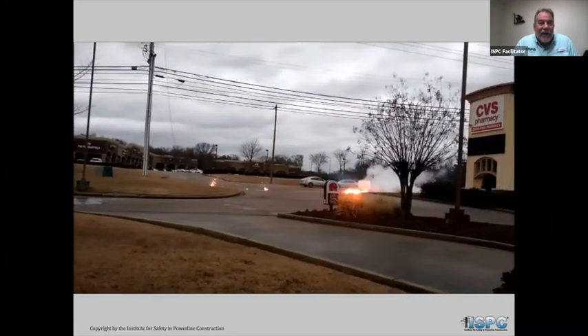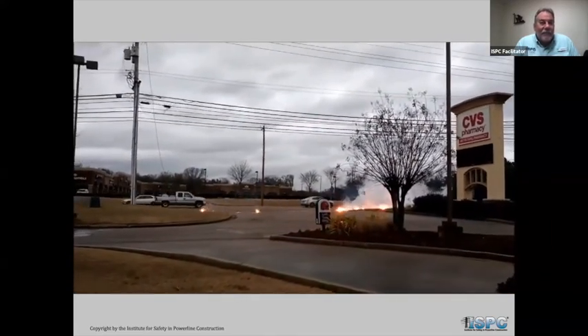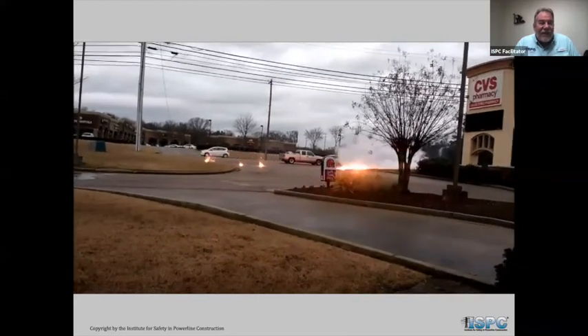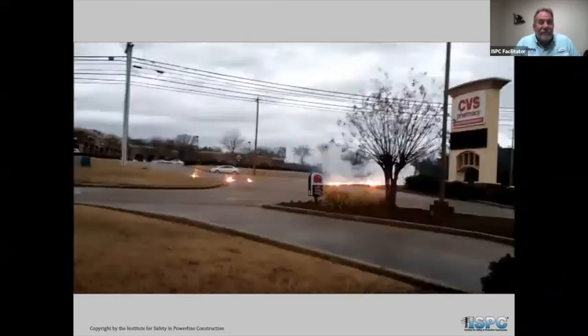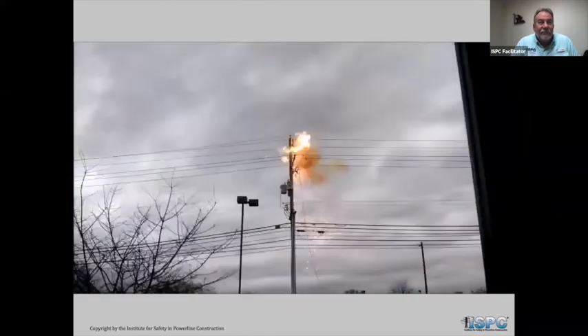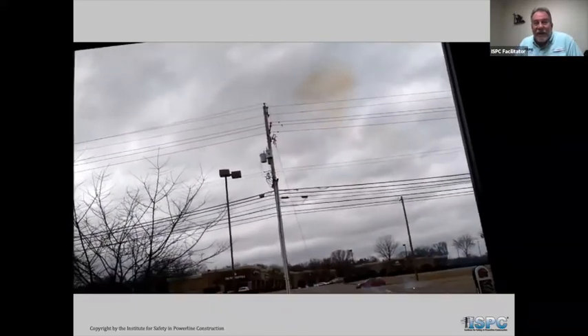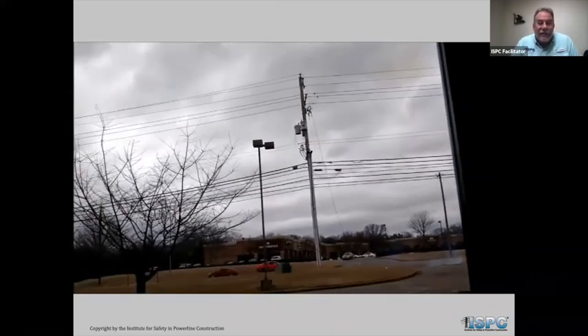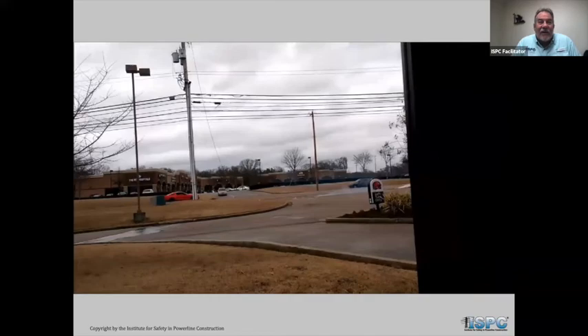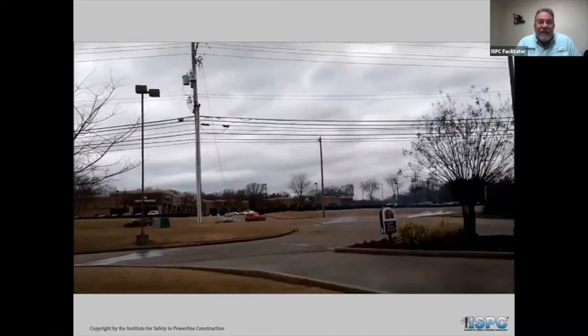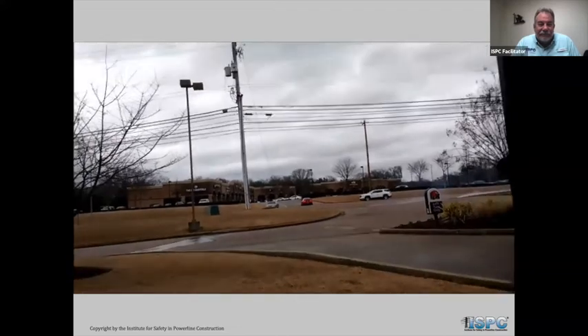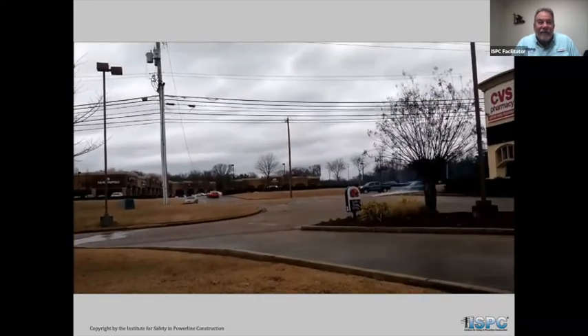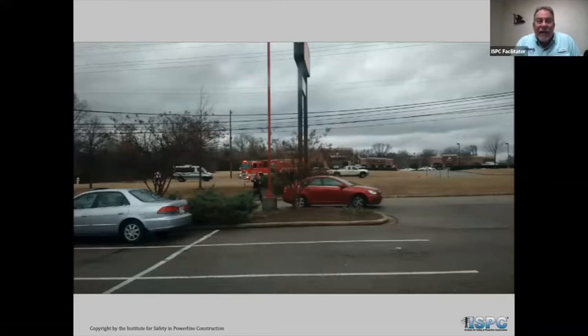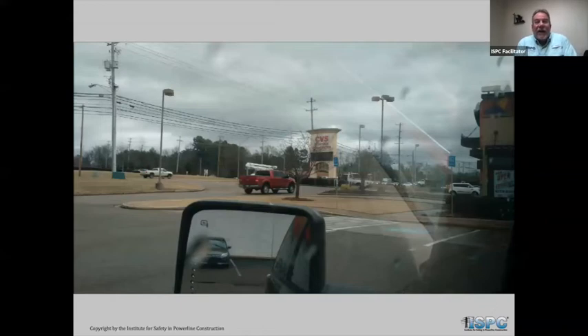During this, you can see that no one drives across it, but here it is, energized again. Yeah, I saw it fall, it came loose from that pole there. So there it just went phase to phase through that 3-phase transformer. So now you see all 3 cutouts are hanging down, but is the line de-energized now? I don't know. It depends on the company's scheme and how many times they want to trip the recloser.